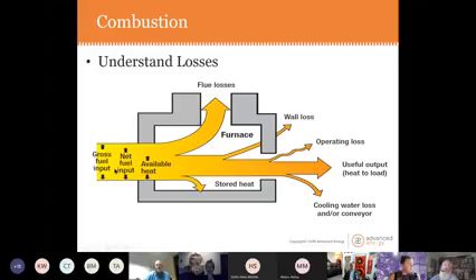When you burn something, it gets hot. When you get hot, you're going to have losses. The building we're in is 80 degrees. This combustion's at 1800 degrees. So you think about all this natural gas comes in, you combust it, most of it goes right up the stack, or a good portion of it. You're going to heat up your furnace. You're going to lose some heat there. You're going to lose some heat here, and maybe a third of the natural gas you combusted actually goes and does something useful to your part or your cookie or your brick or your coating or whatever you may be curing or heating or cooking.